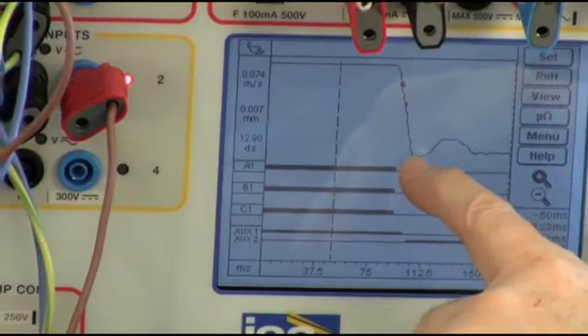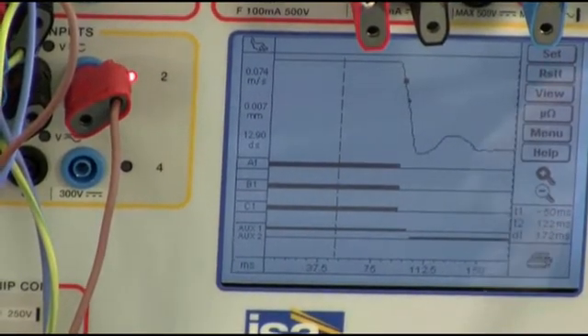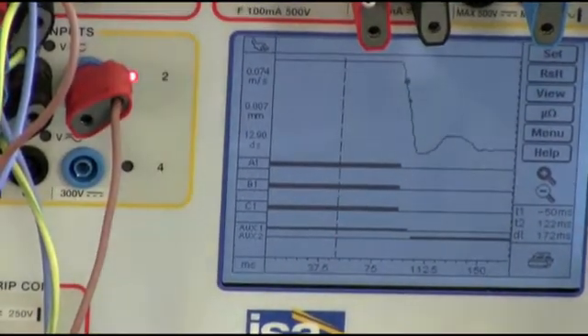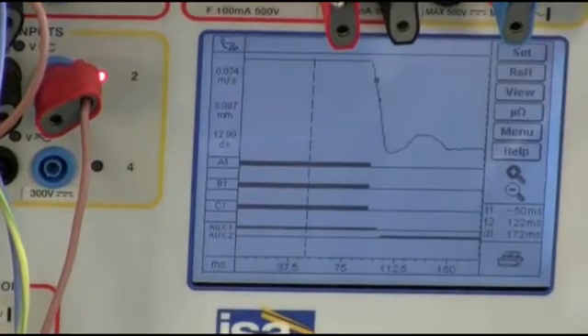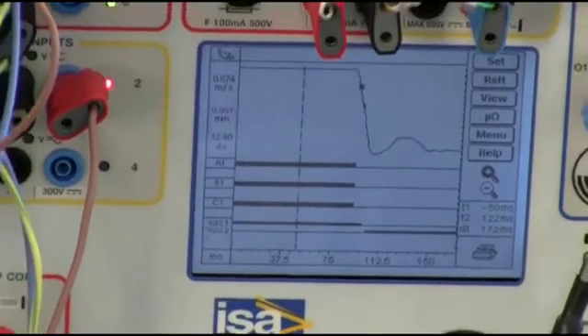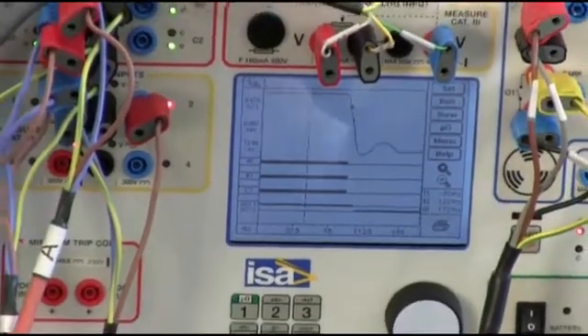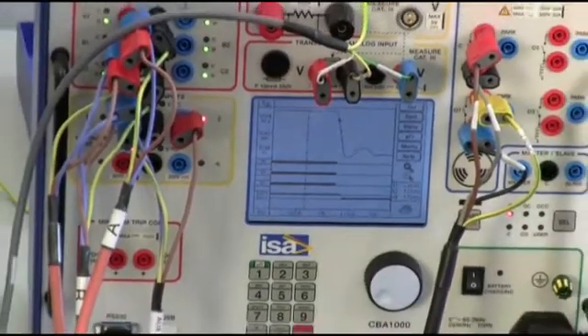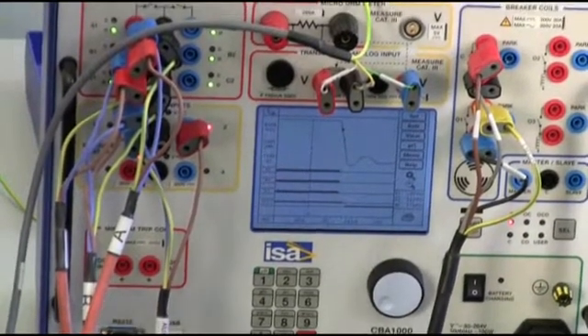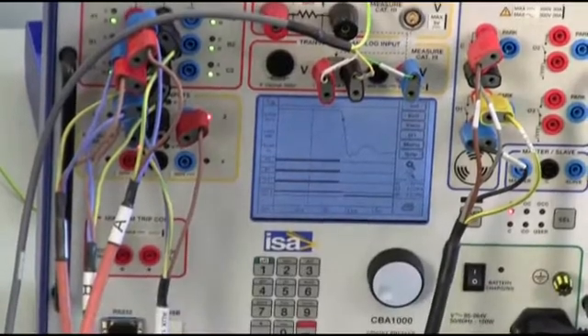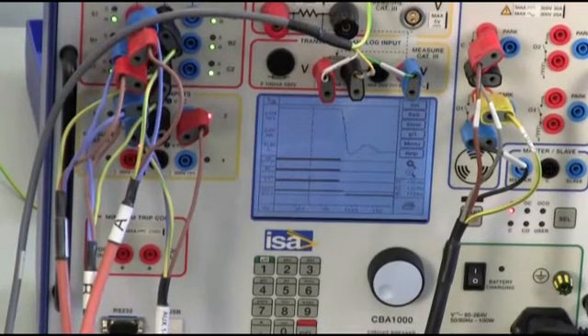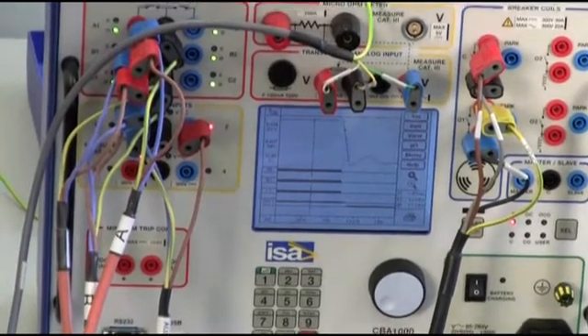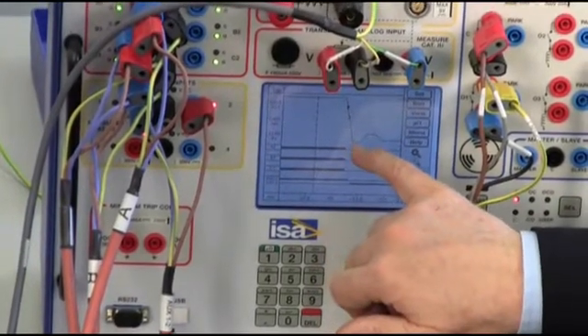Now, this is the normal movement. Why? Because you can understand that there is a huge mechanical energy in all these mechanisms and as the circuit breaker is opened, there is a shock absorber, by the way located here, that is taking this energy and dumping it.